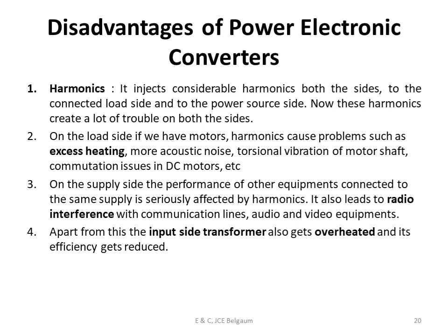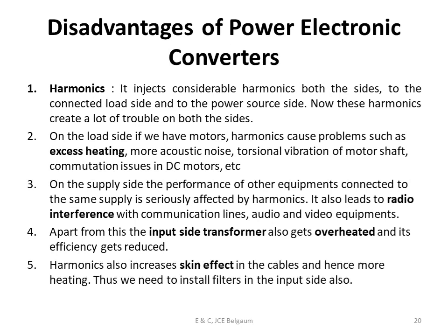Apart from this, the input side transformer also gets overheated and its efficiency gets reduced. So these harmonics have a lot of issues. They also produce something called skin effects in the cables and hence more heating. Thus we need to install filters at the input side.